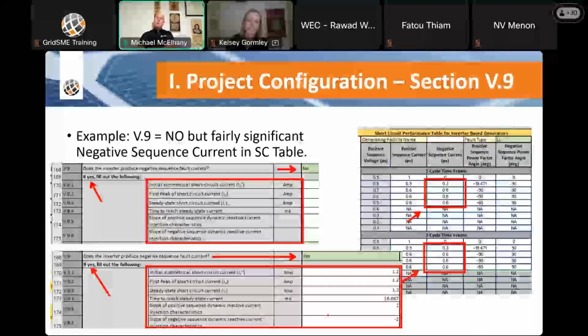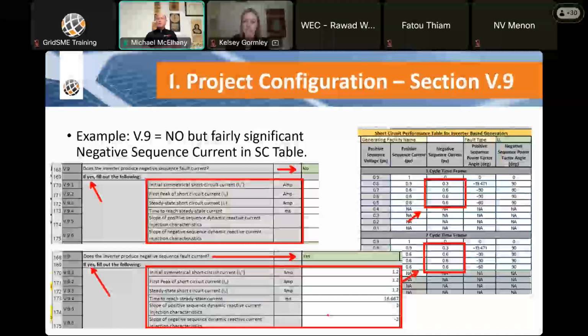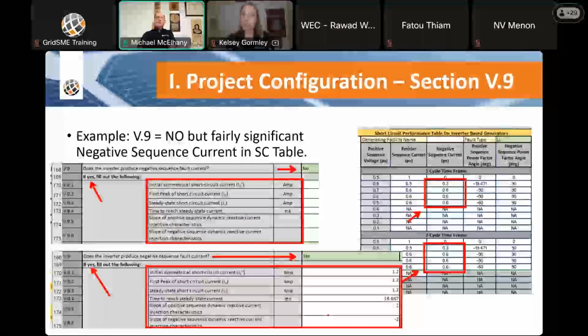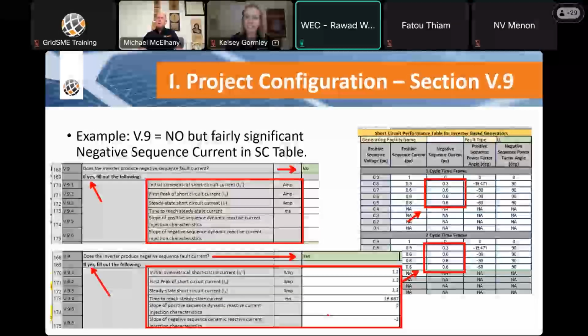Well, again, we worked with the same engineer on multiple projects and had a K factor of 2. And then all of a sudden he said, we need to have a call because we can't do a K factor of 2, because our inverters actually inject 1.2 per unit current. So we had multiple clients that achieved bucket 3 approval with a no, and now we're saying yes. Same kind of scenario where, when we brought this up on a particular project, they came back and said, well, actually, yes, the answer is yes. Yeah, I guess it's one of those things that even happens on the CAISO side, depending on the reviewer you get, things might come up. So, all right, thank you.